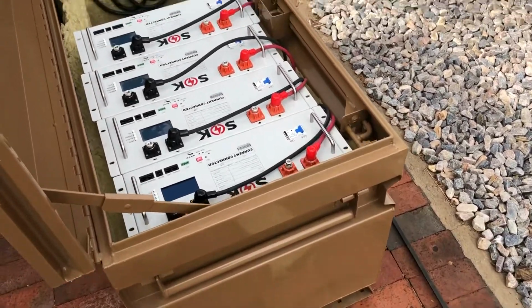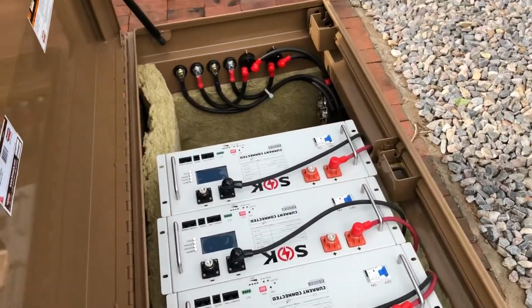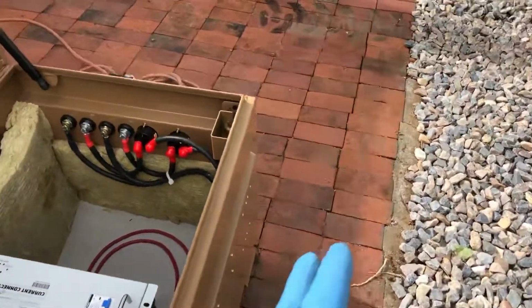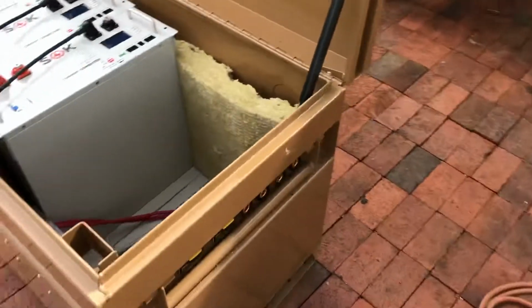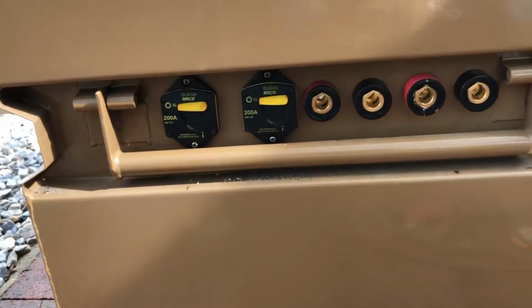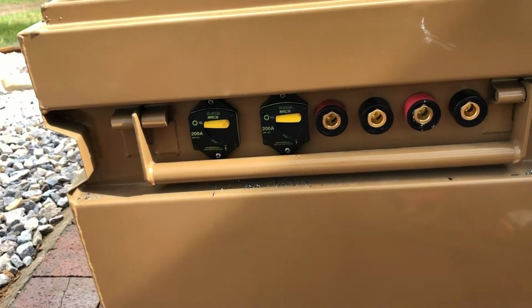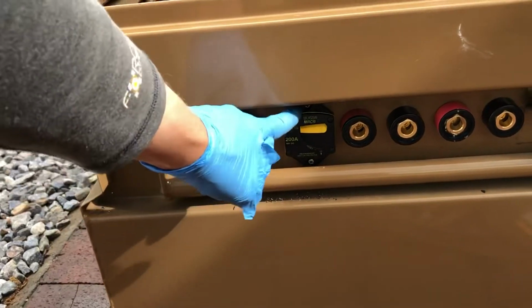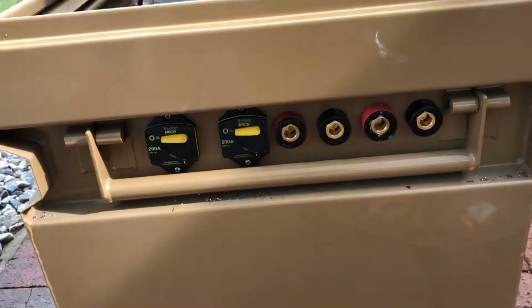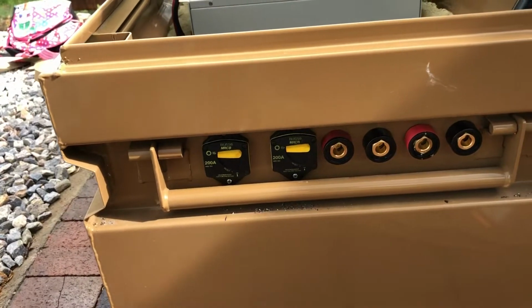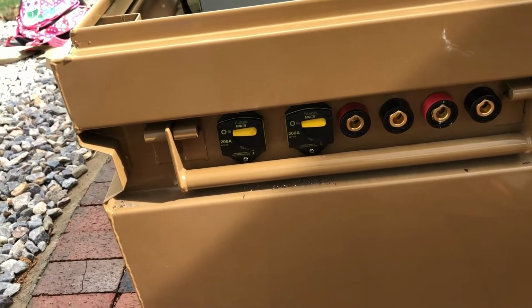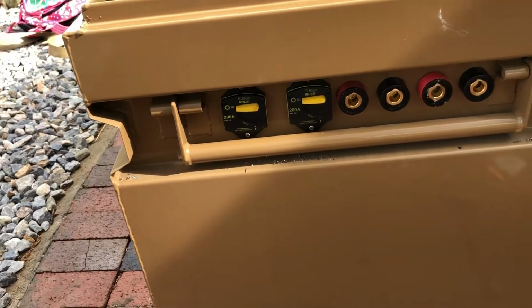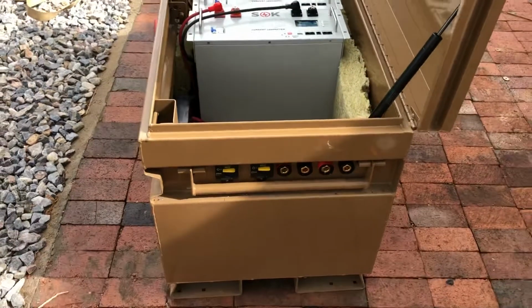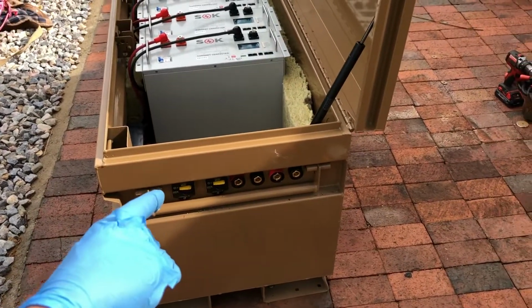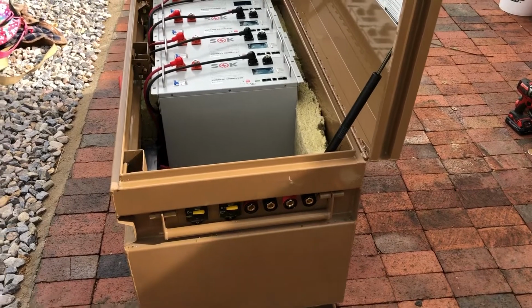It's set up to have two 200 amp outputs, so that's 2 circuit breakers and 2 circuits, 200 amps each. I have 2 8-kilowatt inverters that I'm going to run with this simultaneously, one circuit per inverter.